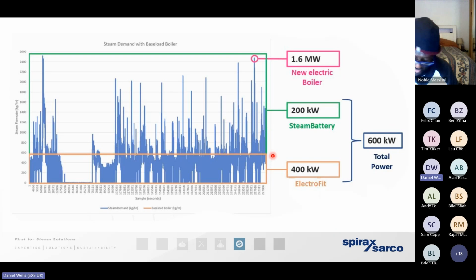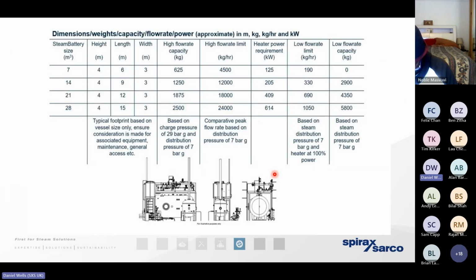And it may then be that a much, much smaller electric steam generator or an electrified existing boiler was able to satisfy the requirements for the base load. And that in turn could mean that we no longer need a significant overhaul of the wider electrical infrastructure. So this just gives you an indication of some of the capacities of those steam batteries. It really comes down to the mass of steam that the client requires and the pressures and temperatures. They generally are bespoke engineered.